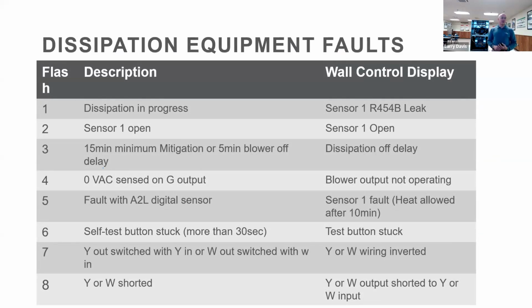It has an LED on it that'll give you the status. If there's a code, it'll flash. If everything's hunky-dory and it's powered up, the light will be on solid. But if there's a fault, any one of these faults, it's going to flash that code for you. Okay.